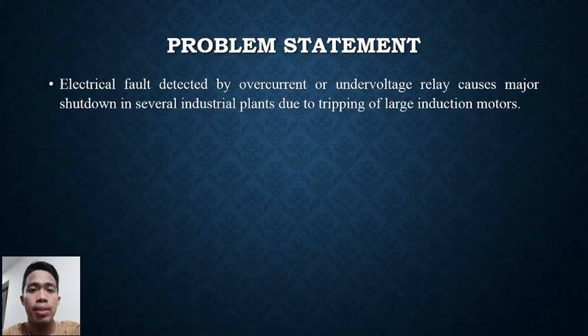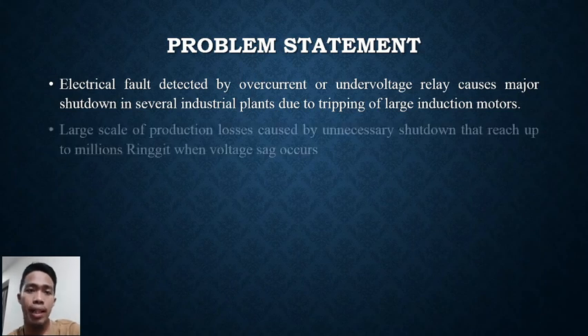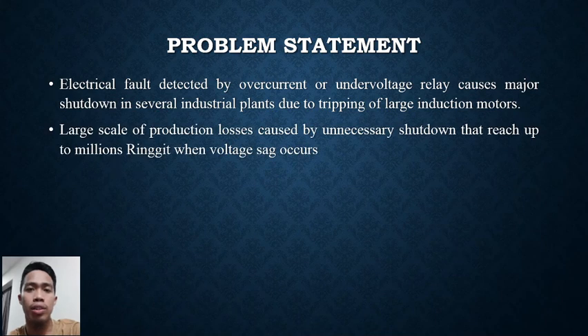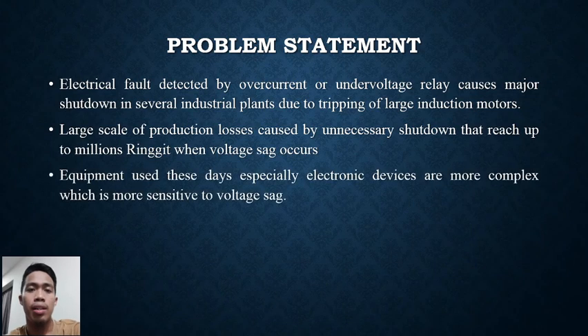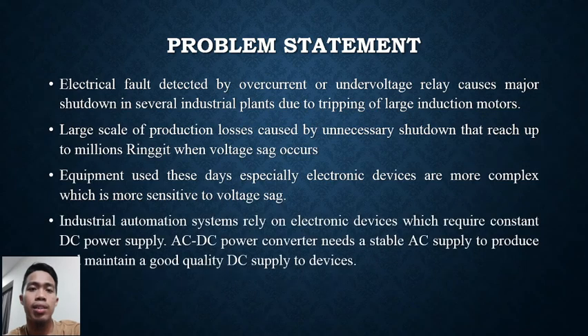I will continue the presentation on investigation of voltage sag and mitigation measures, starting with the problem statement. First, electrical faults detected by overcurrent or undervoltage relays cause major shutdowns in several industrial plants. Then, large scale production losses caused by unnecessary shutdowns reach up to million ringgit when voltage sag occurs. Next, equipment used these days, especially electronic devices, is more complex and more sensitive to voltage sag. And the last one is that industrial automation systems rely on electronic devices which require constant DC voltage supply.